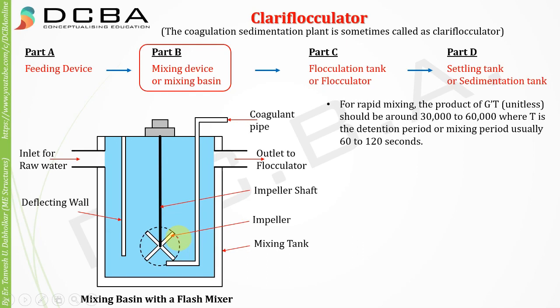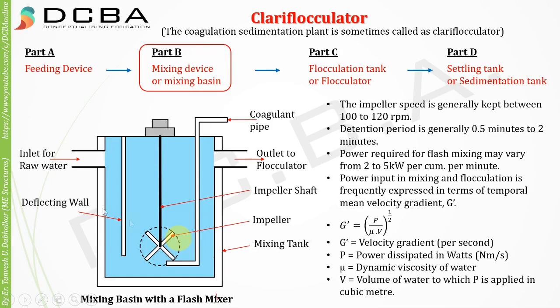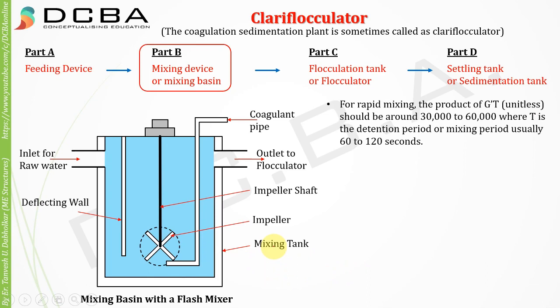The units of velocity gradient G' are per second (s⁻¹). If you multiply G' by time t, you get a dimensionless quantity. For rapid mixing, the product G' × t should be around 30,000 to 60,000.